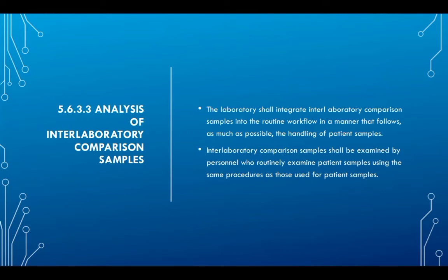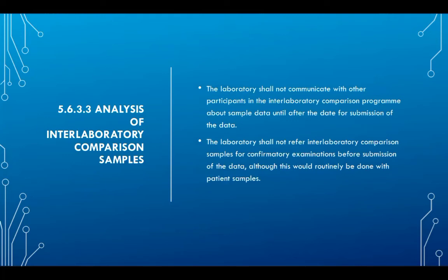Then the important thing is this EQAS sample shall not have any special importance, and the person who is performing patient samples as a routine, that person only shall perform the test on this EQAS sample. It is not like some special person will perform tests. And results shall not be discussed with the other participants of that EQAS scheme in other organizations. It is not like you are organizing a kitty party and in that party you are deciding what results shall be submitted to the EQAS provider.